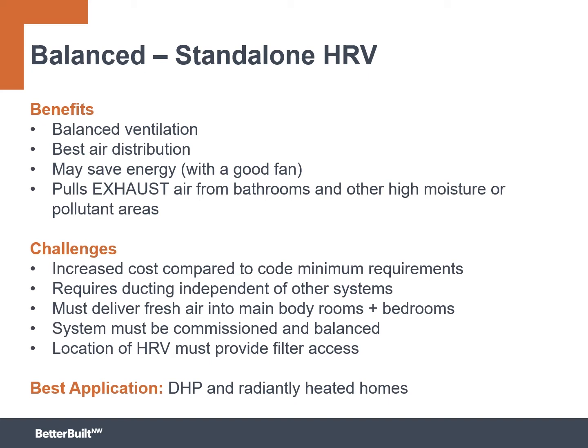And you can pull exhaust air from the bathrooms and other high moisture air or pollutant areas. Again, hopefully benefiting your general indoor environmental quality and maybe reducing the size of the spot or local exhaust fans that are necessary. Challenges, of course, there's an increased cost compared to code minimum requirements. It does require ducting independent of other systems throughout the house. You need to deliver fresh air into both the main body and the bedrooms to really be distributed. And the system does need to be commissioned and balanced.